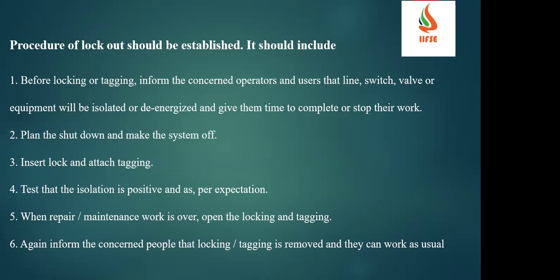Before locking or tagging, we will inform the concerned operator or user in that line, or whoever is using the specific equipment we are going to work on. The equipment will be isolated or de-energized, and they are given time to complete or stop their work. So we will isolate the supply if it is electricity. If it is any pipeline you are doing lockout on, we will remove the complete material inside the pipe, we will drain it. Then plan the shutdown and make the system off. Then insert a lock and attach the tag.